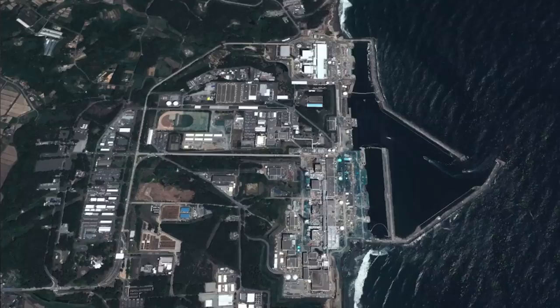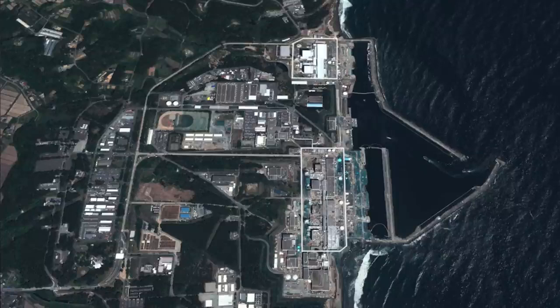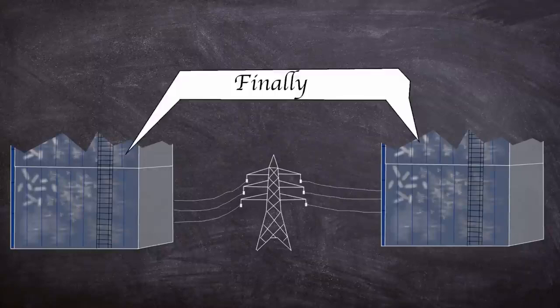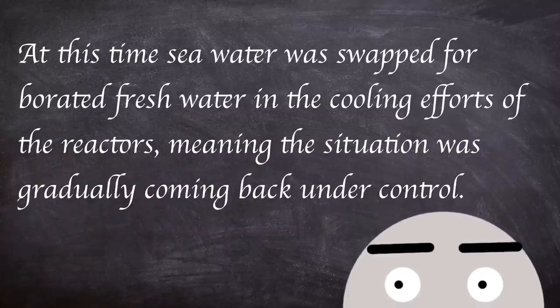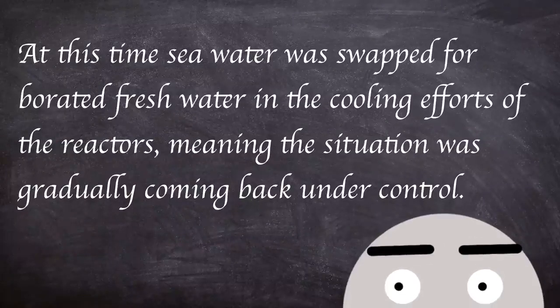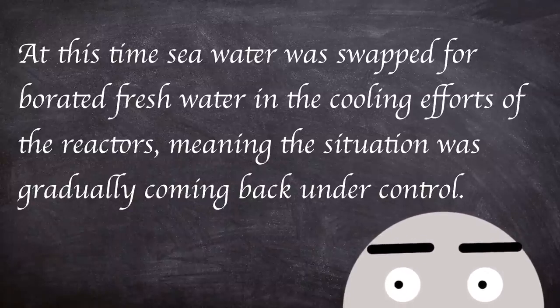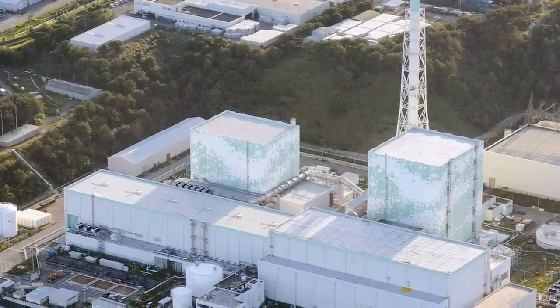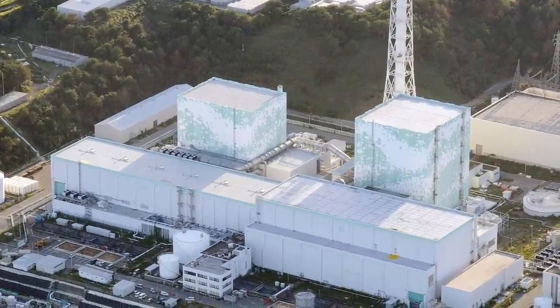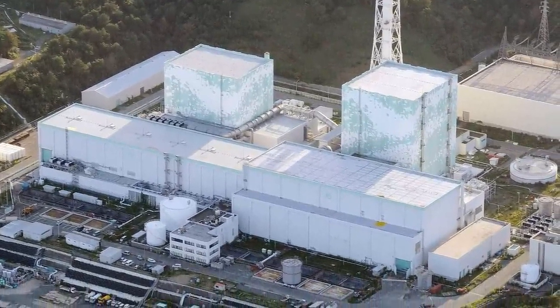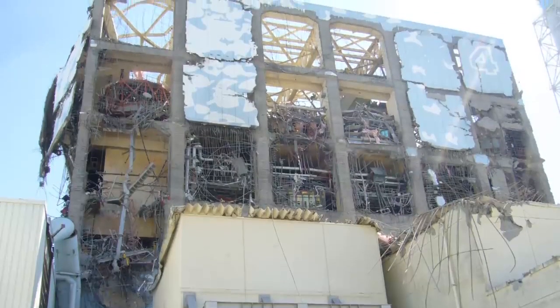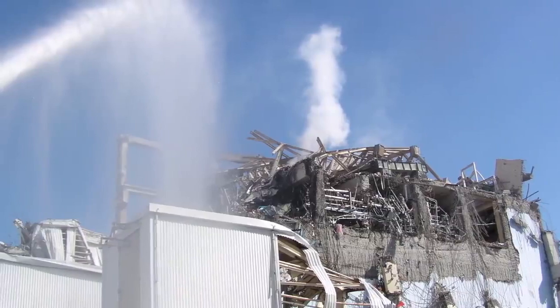Later on into March power was gradually restored to units 1 to 4, with units 5 and 6 receiving power from the only working air-cooled generator. Units 3 and 4 were the last to receive power after being completely cut off for more than two weeks. At this time sea water was swapped for borated fresh water in the cooling efforts of the reactors, meaning the situation was gradually coming back under control. Unit 5 was the first to be put into cold shutdown mode at 14:30 on the 20th of March 2011. This was followed by unit 6 at 19:27 on the same day. However, the remaining units had a long journey ahead as a more stable situation was achieved in April 2012.